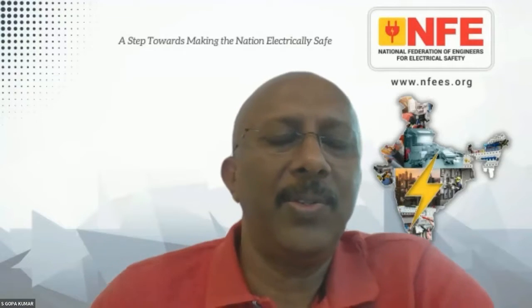Yeah. Gopal sir, I would like to supplement. I attended several telecom PTCC coordination meetings some years back, 10 years back. Now these things are not coming up, I don't know, perhaps because of the absence of almost any overhead telecommunication lines. There is a stringent measure that whenever a parallel feeder, say a 110 kV power line feeder, trips or something happens, there will be induction in the telecommunication lines. That's the purpose. That is electromagnetic interference. Any people who work on a dead line parallel to any EHV line can suffer damage due to induction from that line. That's why parallelism should be avoided in general.